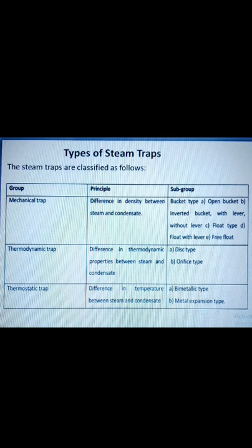Now the second one is the thermostatic trap. These remove condensate through the temperature difference of steam versus the liquid phase. The valve is driven through expansion and contraction of an element that is exposed to the heat from steam or condensate. These traps need a temperature drop below the saturation curve to open and remove condensate. They can do this by a filled element, bellows, or bimetallic element.